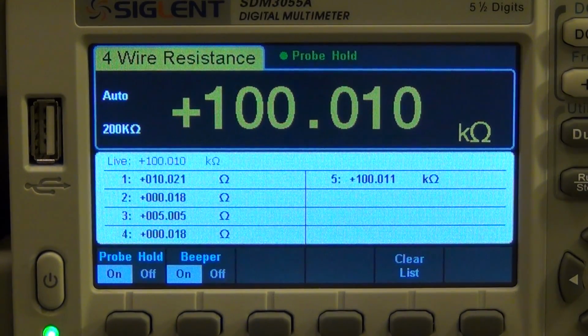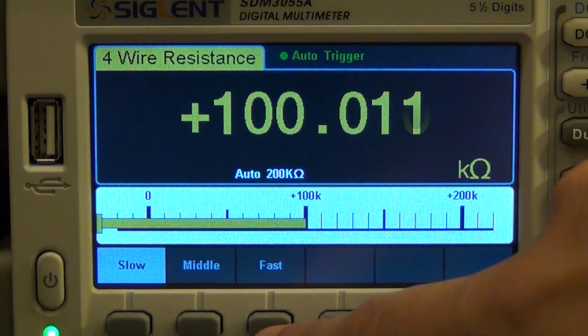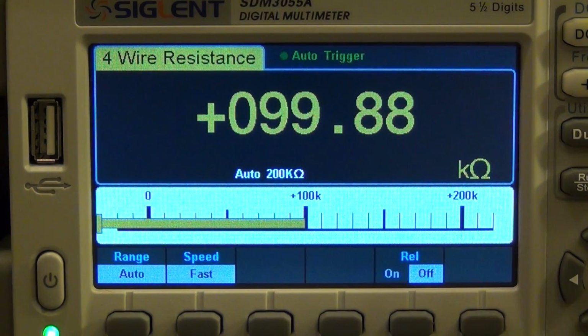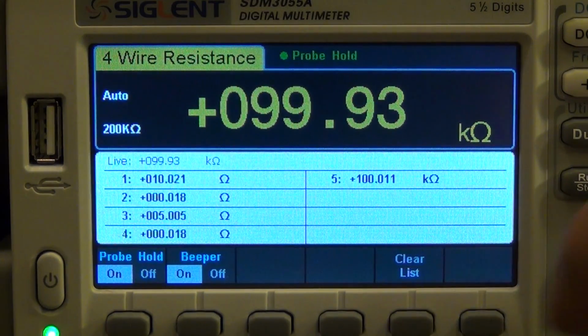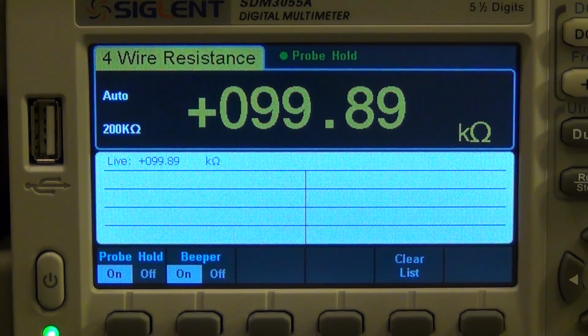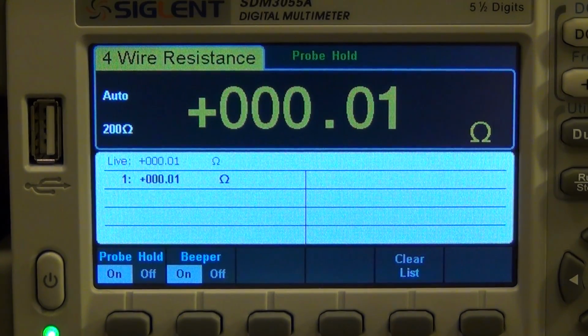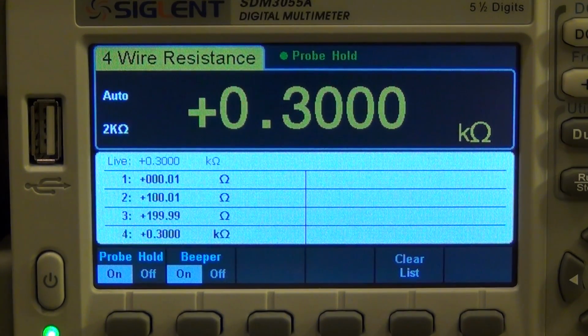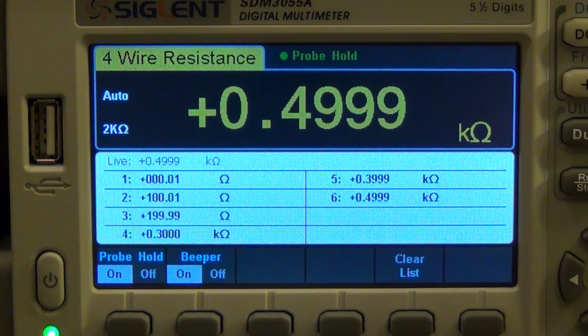Again, my only complaint, just the speed. It's a little bit slow, and it takes its time. Right now it's on slow measurement mode. So if I go ahead here and change the speed to fast, it is going to do the measurement, of course, much faster. And I can go under hold again and clear the list. We can try again. 0. There you go. You can see it's now much quicker. There, see? It does it as soon as I change. There we go. Very nice. So if you're a little bit impatient, you're going to have to make a bit of a compromise between speed and accuracy. But other than that, in this mode, it's pretty quick.